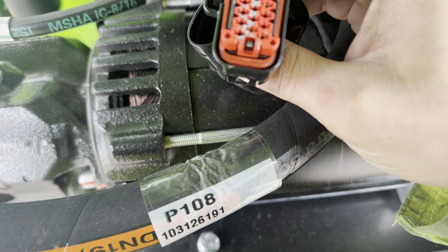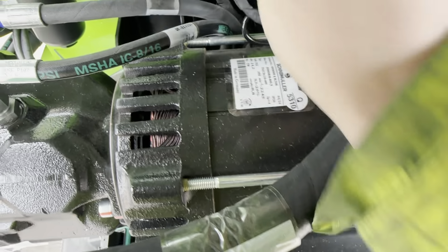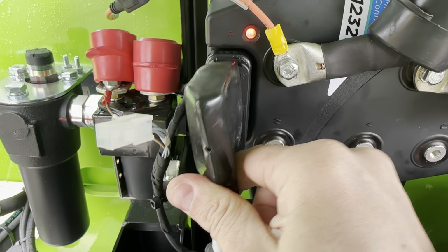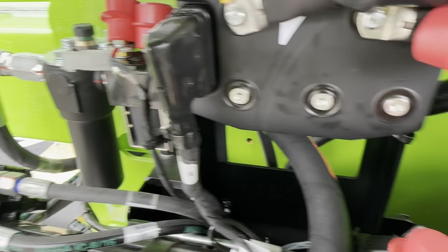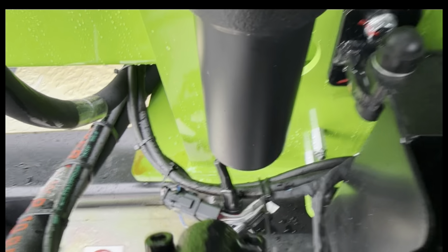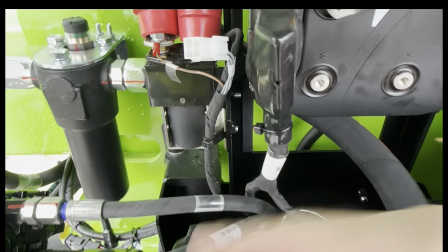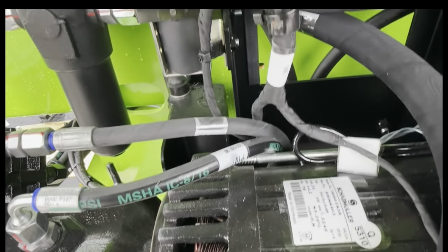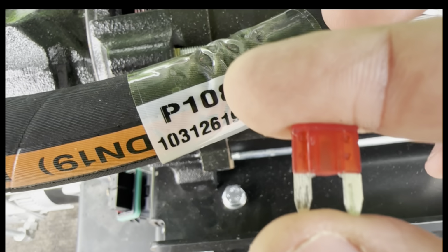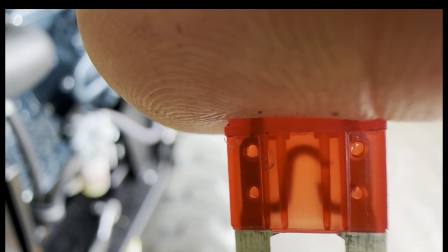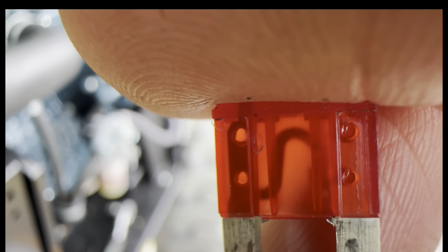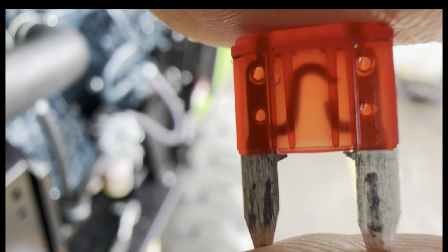Okay, just looking at the wiring to see why that would fail, and the cables here seem to run fine. All right, let me continue with the investigation and we'll let you know. So those cables are looking good. I checked the relays here, connections seem to be okay. This one is looking good. I found a blown fuse here. Visually it doesn't look like it's really gone. Oh, actually, now with the camera I can see it right on the line there. Okay, so it's definitely gone.